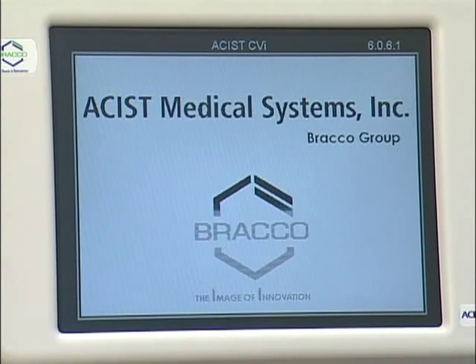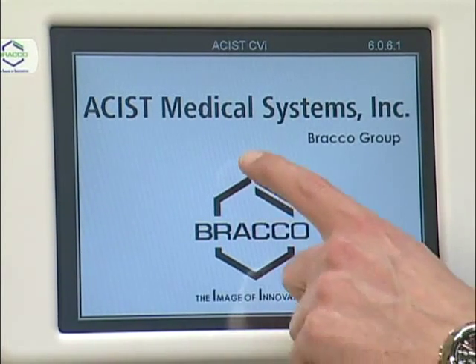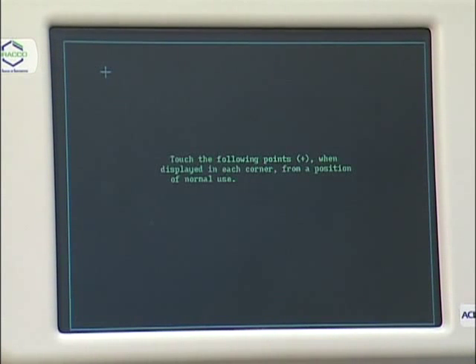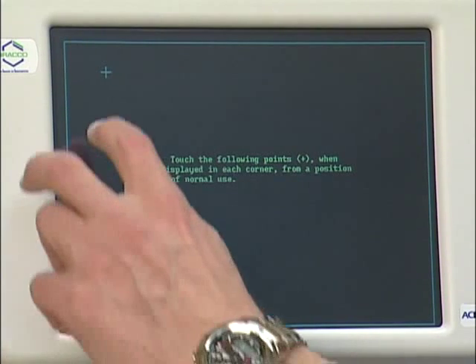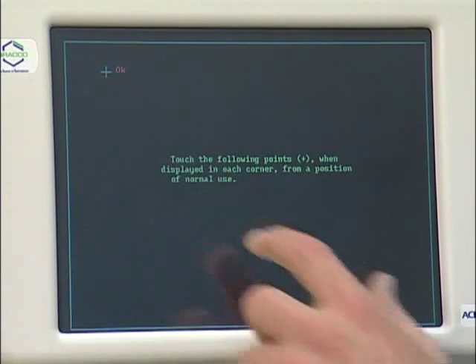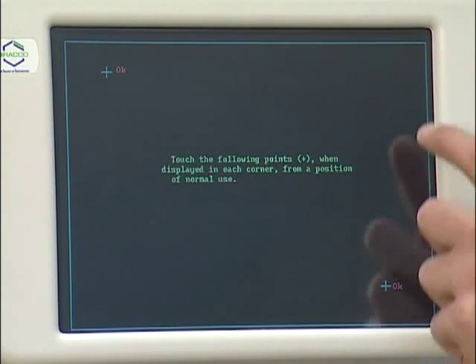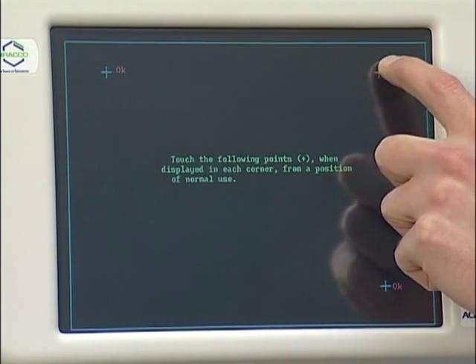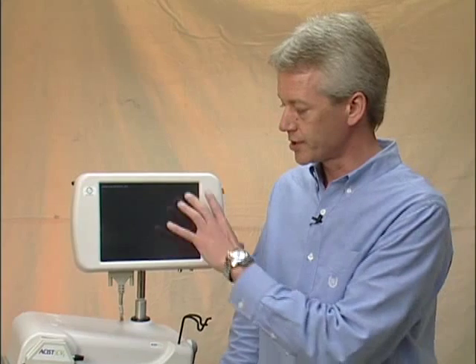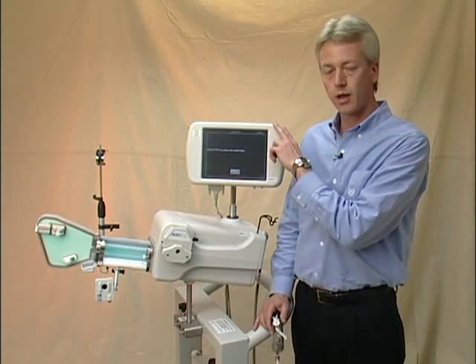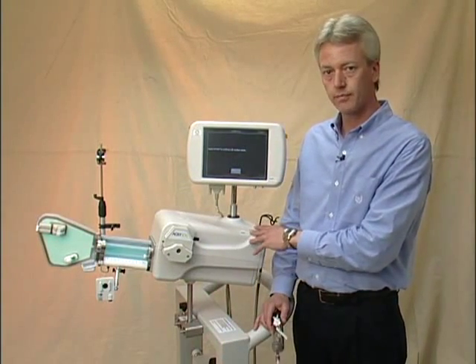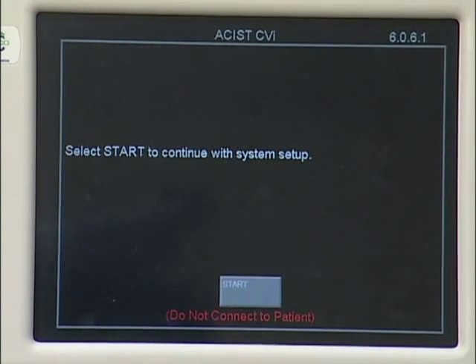To initiate the calibration of the touchscreen, the operator will touch the Bracco ACIST logo screen once, and that will boot them into the calibration mode. The operator is instructed to touch the crosshairs very precisely in the top left, the bottom right, and the top right areas of the screen to calibrate the screen. Once the calibration is complete, the system will reboot. Now this control panel is calibrated to this injector head, and now we'll begin with the setup of the system.